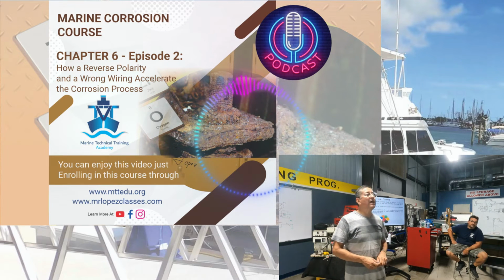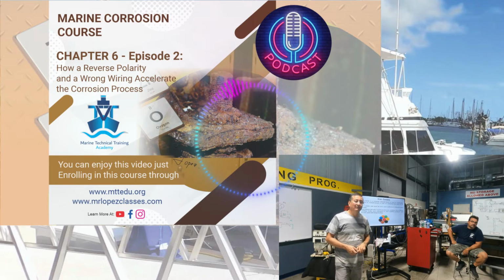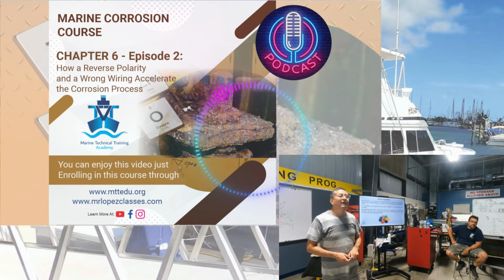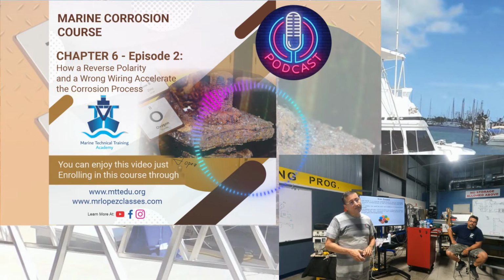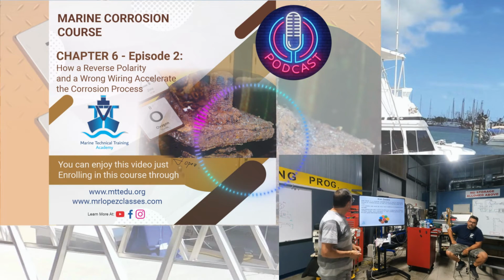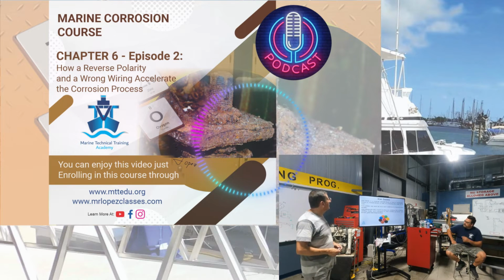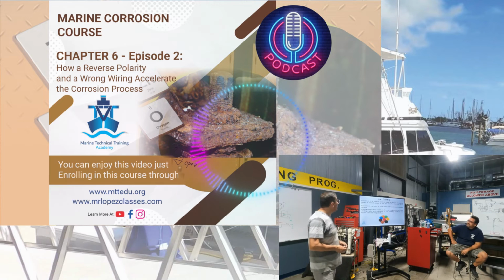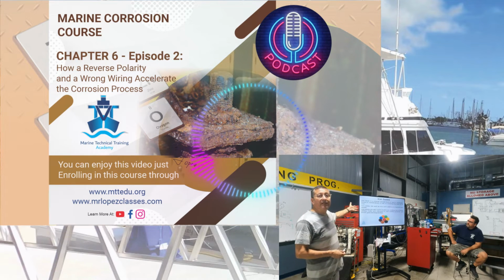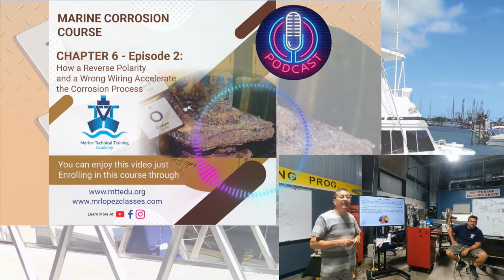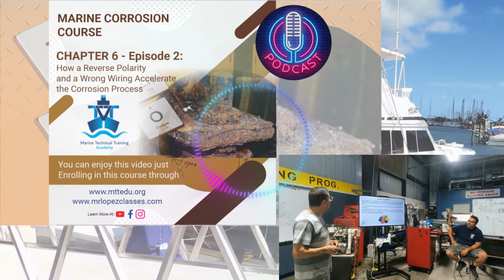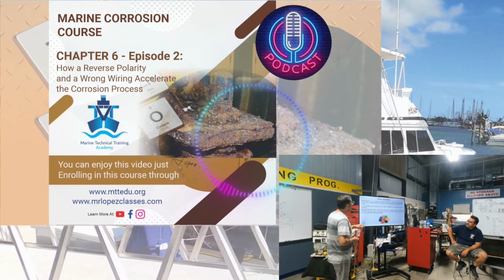This is the AC panel, this is the main breaker, and those are the individual breakers. The capacity of the main breaker, in this particular case, is 30 amps, and the capacity of the galvanic isolator is 30 amps. This one should be equal to this, and also the capacity of this and this should be equal to the capacity of the output breaker of the generator. 30 amps, 30 amps, 30 amps. It's exactly the same for all of them. Okay, this is the ground.